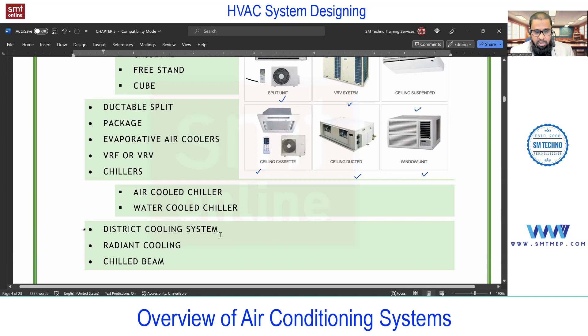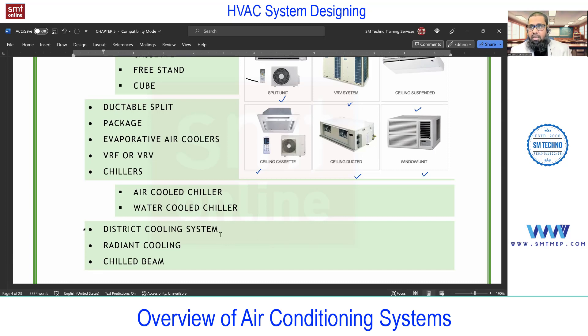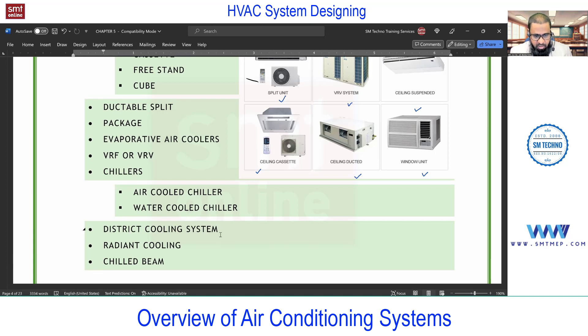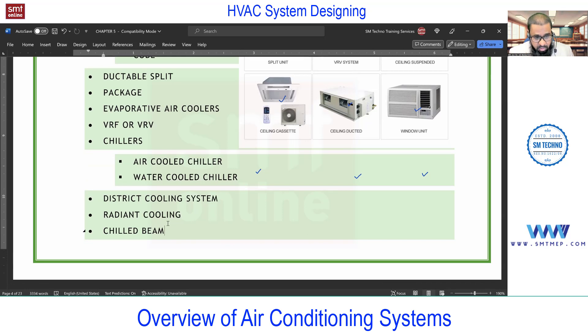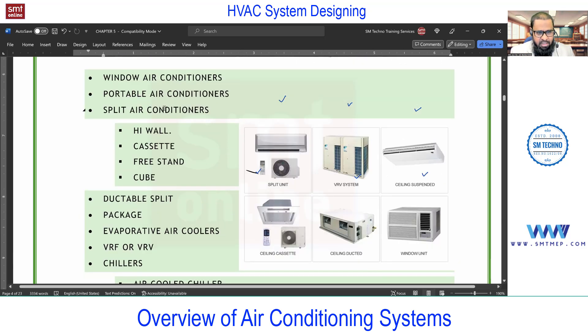Next is district cooling system — it's like a big chiller plant located away from the city, acting as a service provider. They supply chilled water through insulated pipes, similar to how municipal water is supplied. In the building, this chilled water is used to cool the air using fan coil units and AHUs. Next is radiant cooling — we'll discuss in detail. Finally, we have chilled beam — also a new concept in the market. Each of these systems will be discussed in detail.